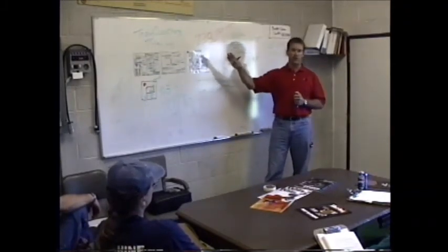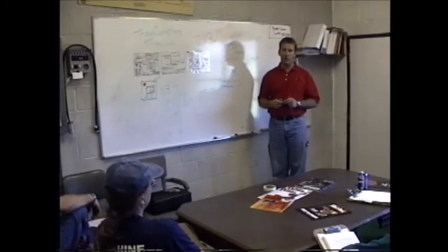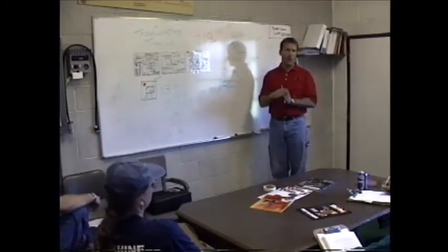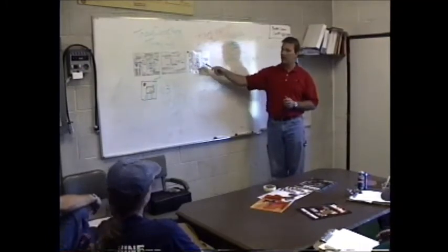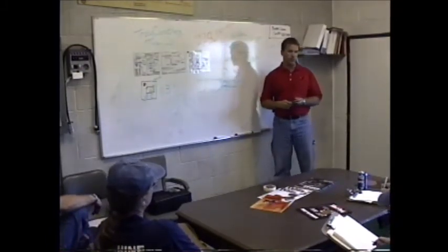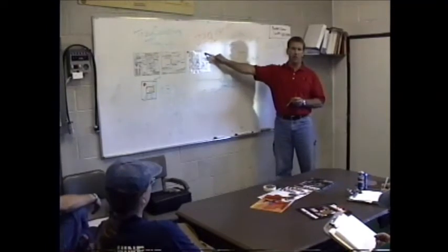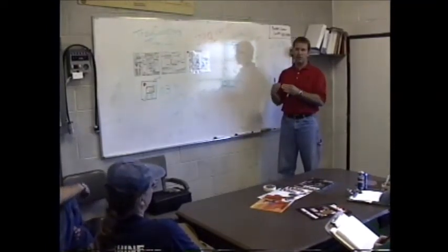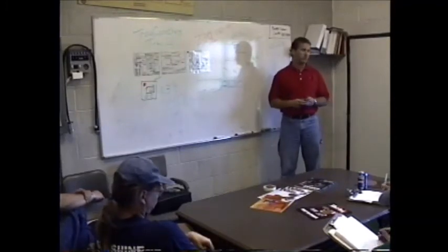Okay, so that inlet valve can open and close 4 times a second to make sure that that air compressor pressure is exactly what the water pump pressure is. That's how that balancing act takes place. So this whole area here, all these controls, act like the cruise control for the air compressor. If you want to think of this like the carburetor, it's going to base that pressure rating like speed for your car. If you set your car at 65 miles per hour, your cruise control looks at your speed.